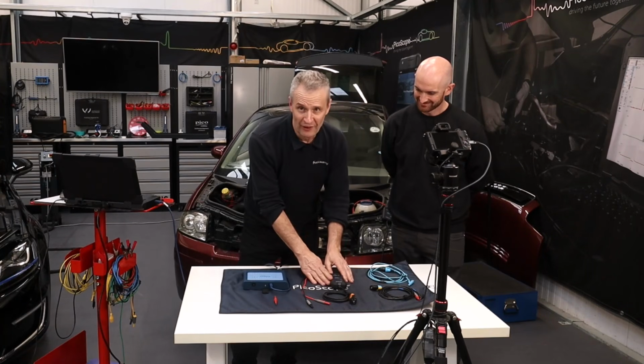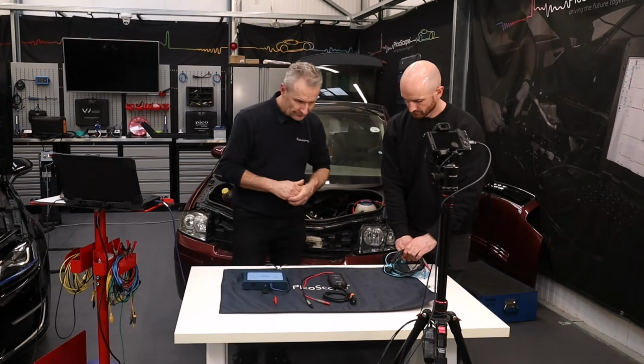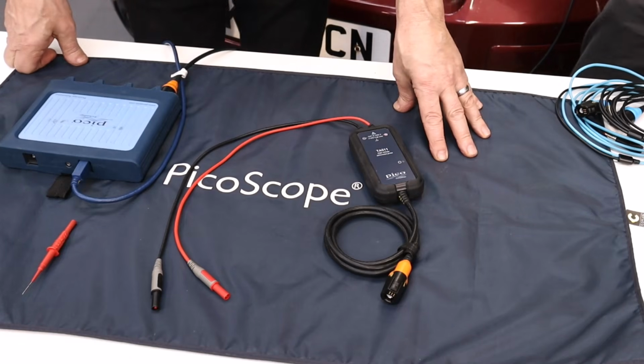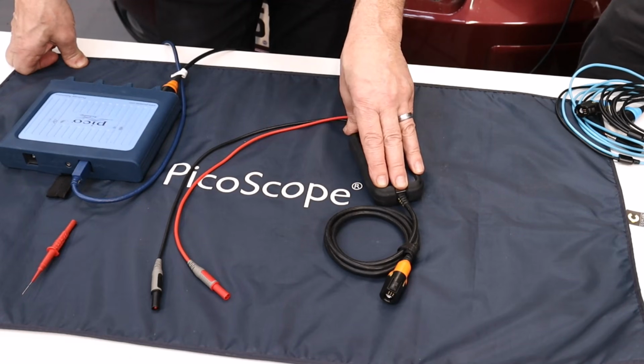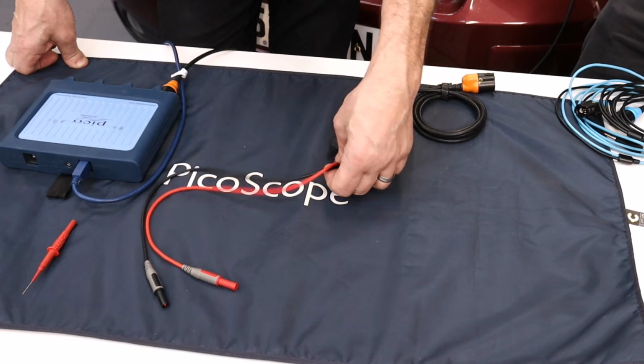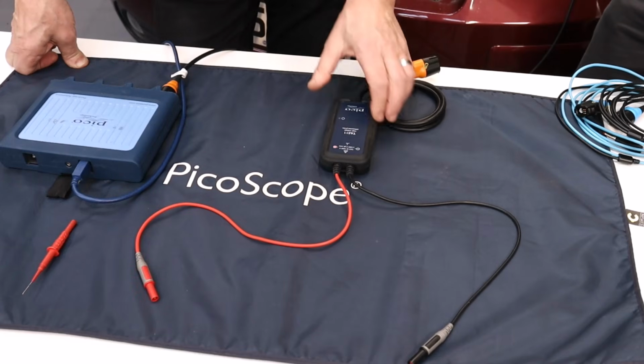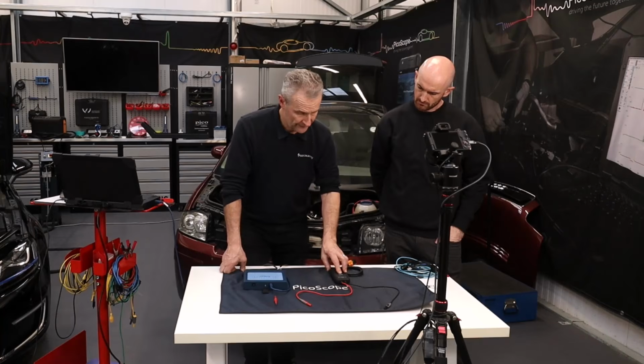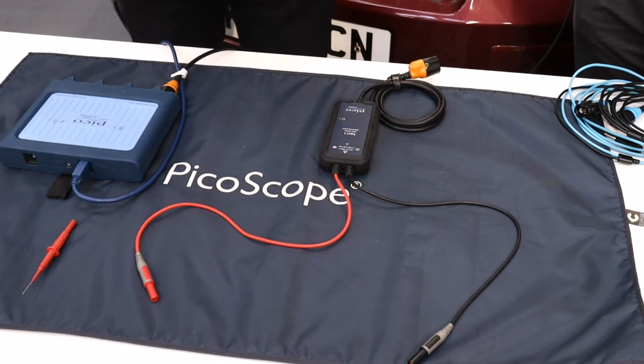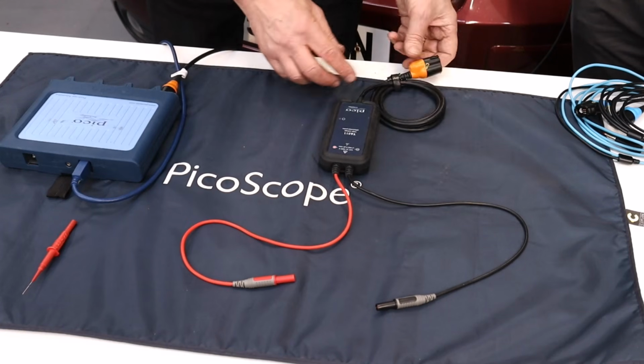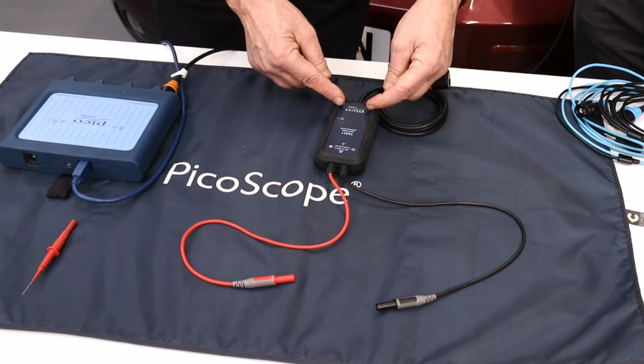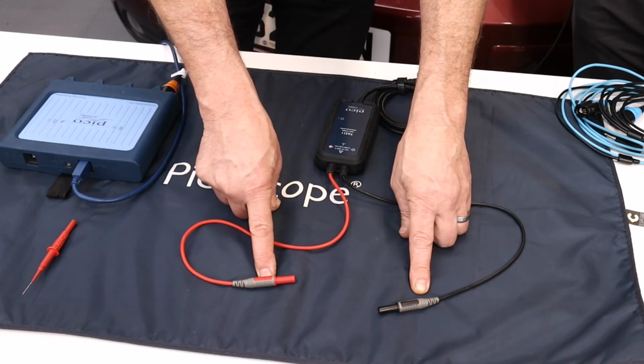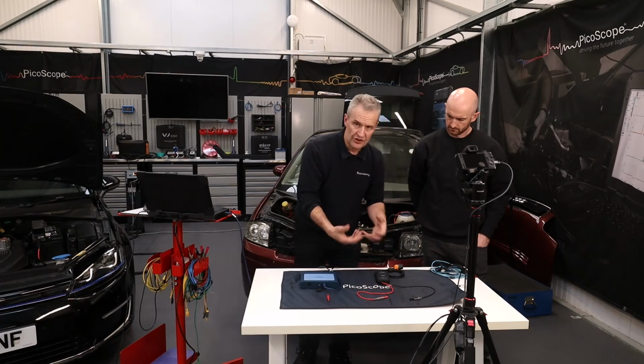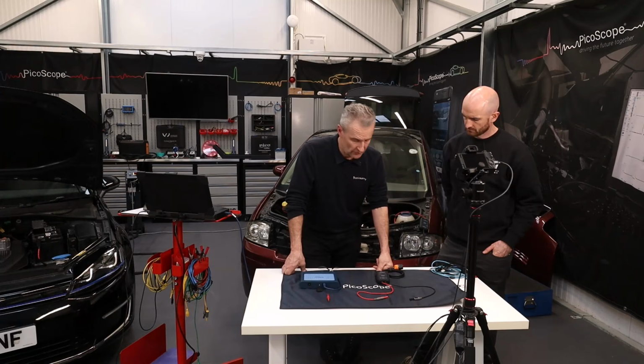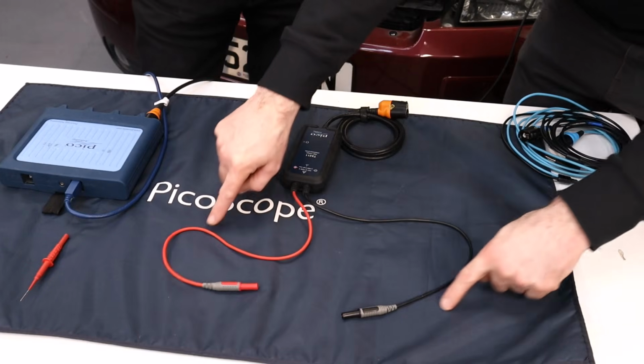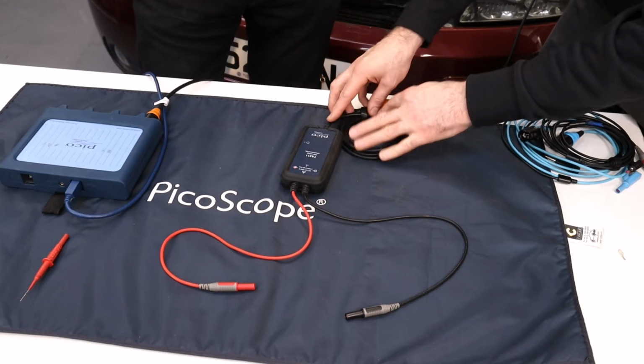And then we finally get to what I wanted to talk about, which was the differential probe. So here then, this is kind of your ×1, ×10 features, all wrapped up into one probe with additional features as well. So let's start with attenuation first of all. The specifications on this are that we can measure up to a maximum of 1400 volts. And throughout here, protective impedance, so from our test leads that are connected to our high voltage component, all the way through to the BNC end, we have stages of protection that ensure that any high voltage that is measured on these 4 mm leads will never reach this point here, such that we would get either an erroneous measurement or a dangerous voltage. I suppose you could almost say that any voltage you measure on these leads pretty much stops there. Absolutely. And then what you measure here is a low voltage output.